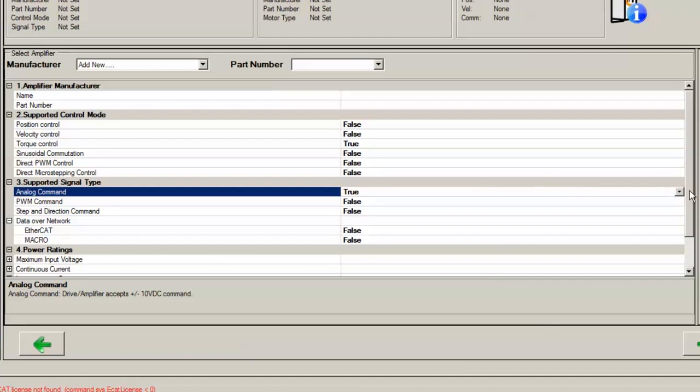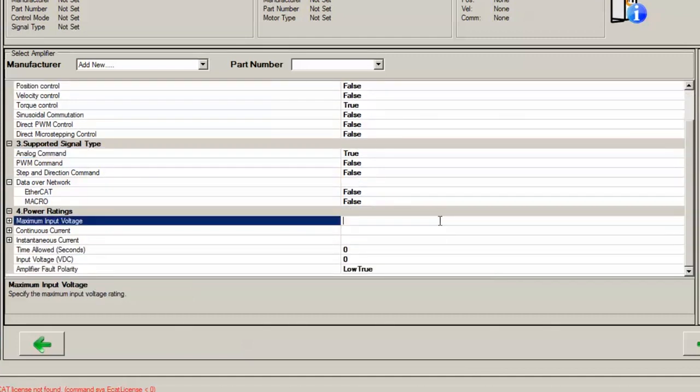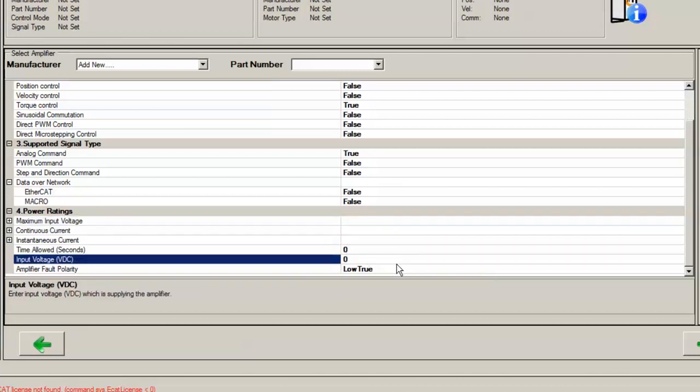Then you need to specify your maximum input voltage for the drive, continuous and instantaneous currents in units of amps, the time allowed at instantaneous current, the input voltage also known as the bus voltage in volts DC, and then the amplifier fault polarity. This is usually low true for Delta Tau amplifiers.